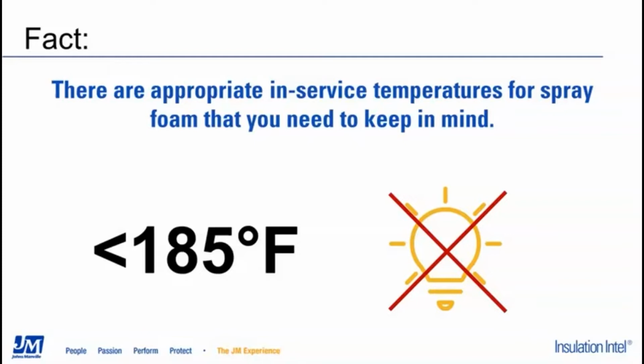There are several other items that come into play with heat-producing apparatus or elements in a building construction environment: the heat flue off of the HVAC, or the heat flue off a chimney or fireplace. But with any of those, we want to avoid being in contact over 200 degrees, 185. Go ahead.